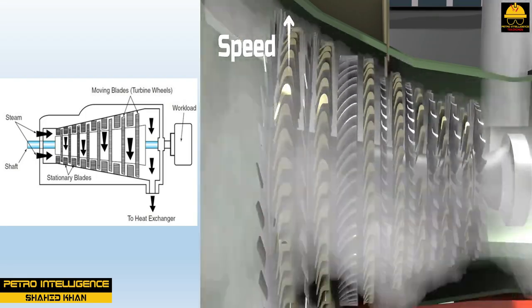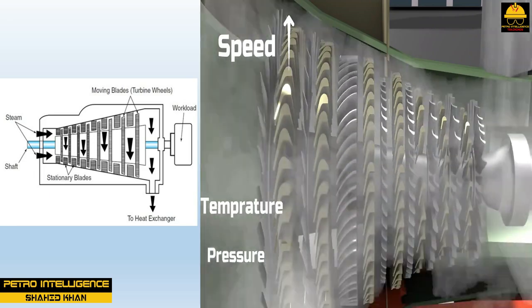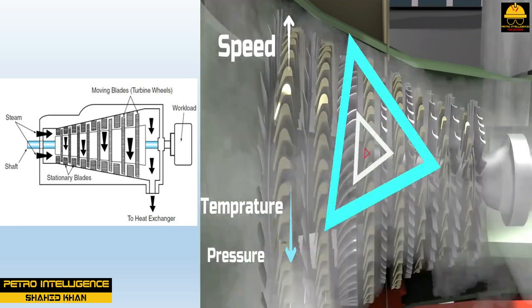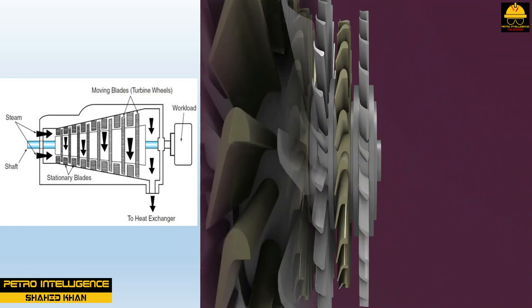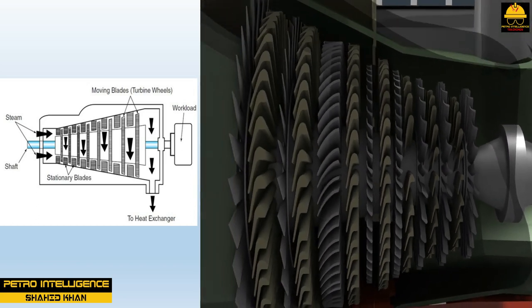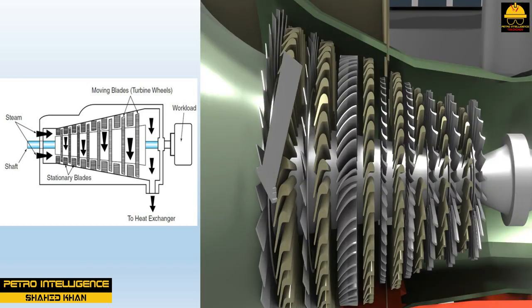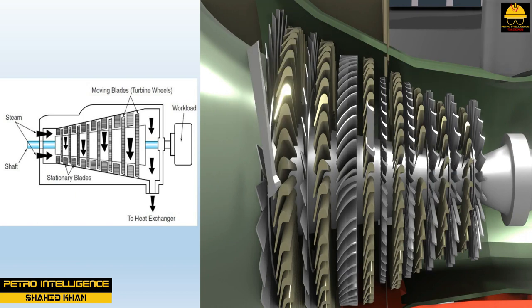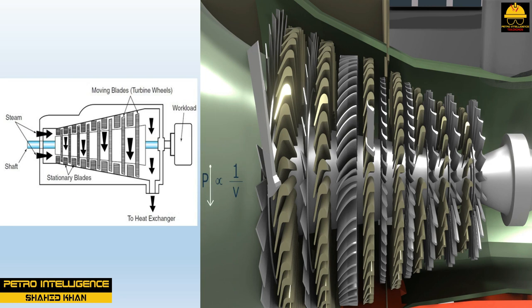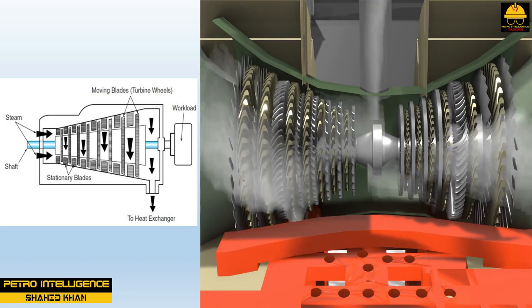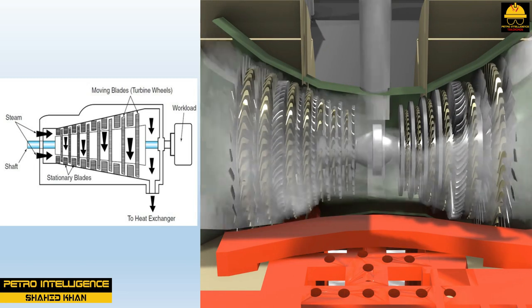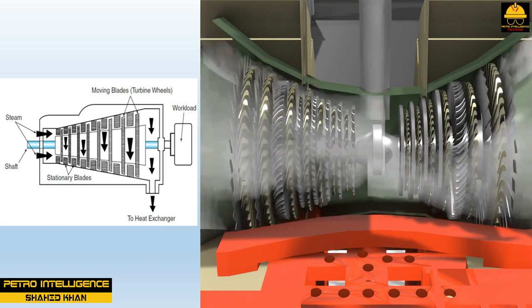As high pressure steam enters a turbine, it passes through a device called a nozzle. Nozzles restrict the flow and increase the velocity of the steam. The nozzle directs this high velocity steam against the blades of a paddle wheel, causing it to rotate. As the steam passes through alternate sets of fixed and revolving blades, it constantly expands as it moves along. The rotating paddle wheel is attached to a shaft, and the blading and shaft together make up the rotor. Impulse or reaction movement occurs as the steam strikes the rotor, converting steam energy into mechanical energy.